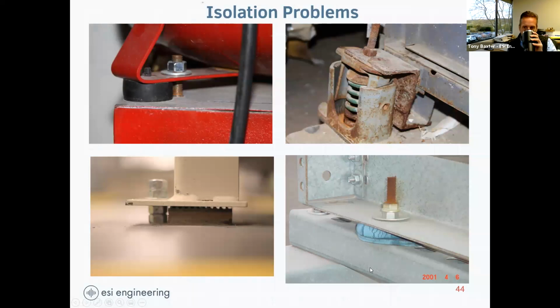When I was an undergrad, Doug from Centec came and showed us at PKI restrained isolators like this, and said when we got into the field, never allow anybody to use these. I've spent over a decade telling people not to do this—it's been bold-faced in our reports—because we go out in the field and still see them. So I'll reiterate Doug's wisdom: never allow your clients to use housed restrained spring isolators. Restrained spring isolators can work, but not the housed ones—they never work. Check the ones at PKI. I'm sure they're still terrible—we used to do that tour, going around PKI to see how not to do noise control.